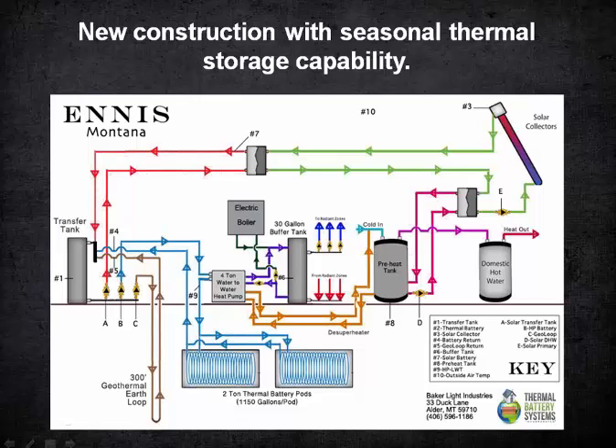So what we're learning is how site-derived energy systems can be configured so that we don't invest so much money on the front end in active energy infrastructure elements—anybody could design one that does amazing if you put enough source energy element in it. But what we want to define is where's the bottom, and what's the minimal amount of source energy elements we could put in that would still meet, let's say, an arbitrary COP set point—say someone wants the system to achieve an annualized COP of 3.5 or greater.